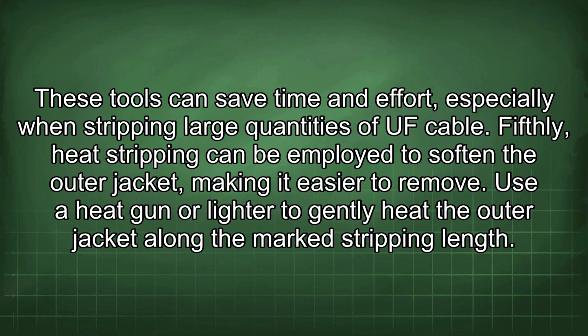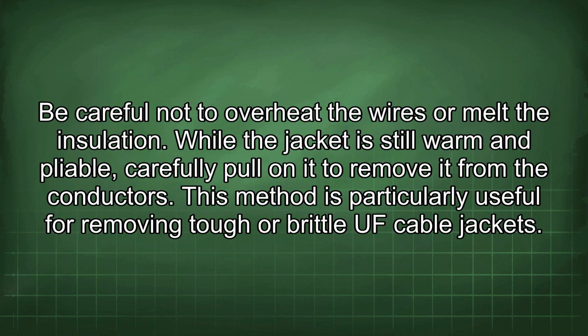Fifthly, heat stripping can be employed to soften the outer jacket, making it easier to remove. Use a heat gun or lighter to gently heat the outer jacket along the marked stripping length. Be careful not to overheat the wires or melt the insulation. While the jacket is still warm and pliable, carefully pull on it to remove it from the conductors. This method is particularly useful for removing tough or brittle UF cable jackets.